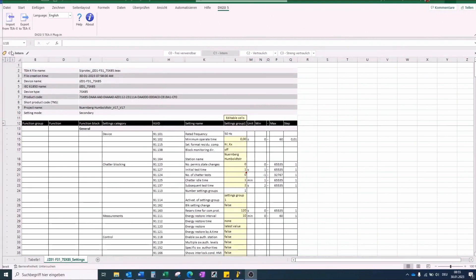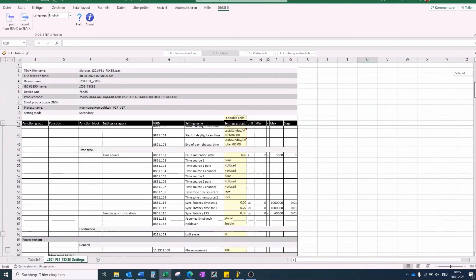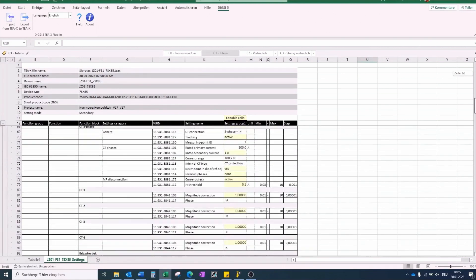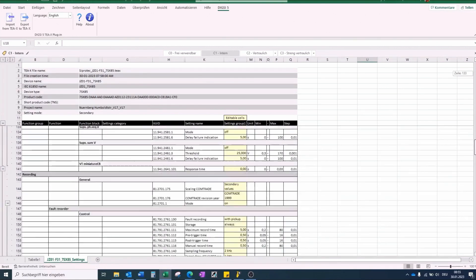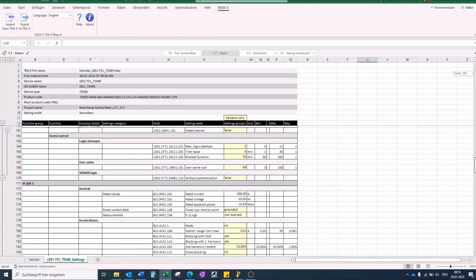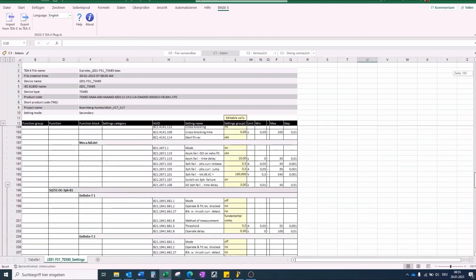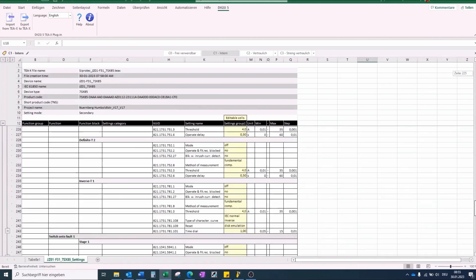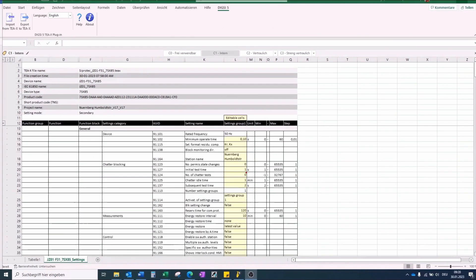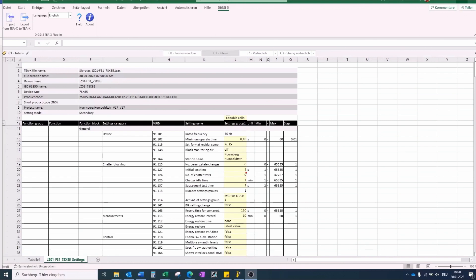Here you can see the clear representation of the setting parameters. The values can be set in the yellow cells of column L. As base for the setting value, we can use the exported parameters from the 7SJ641. See Migration Step 3.